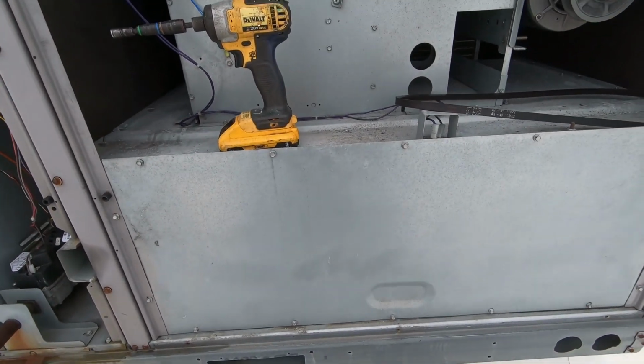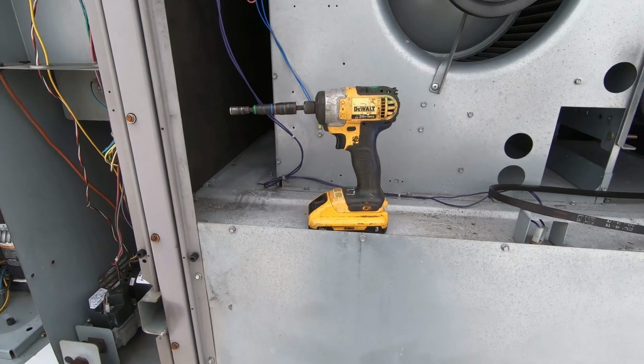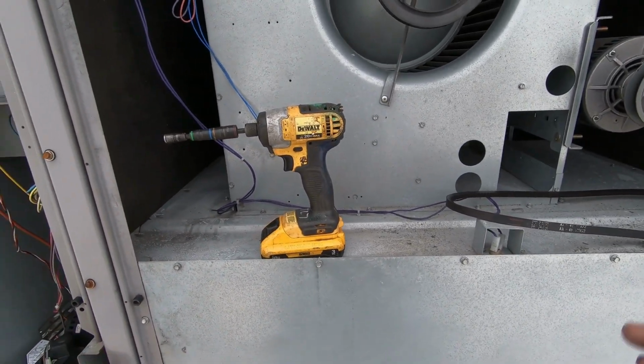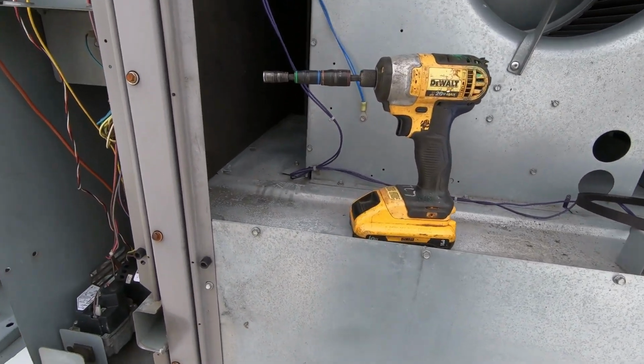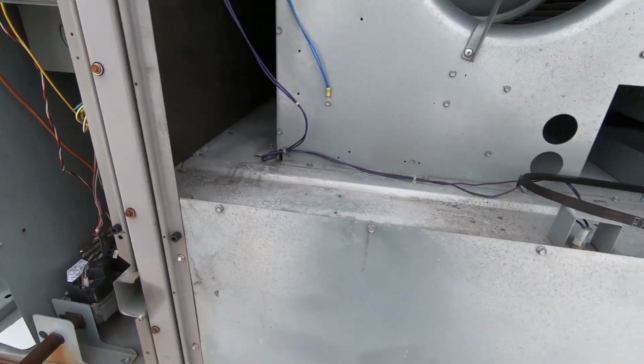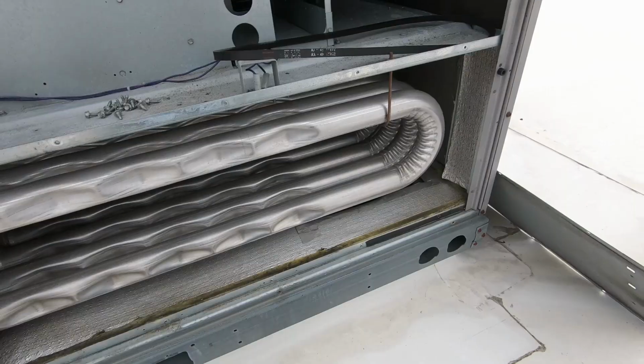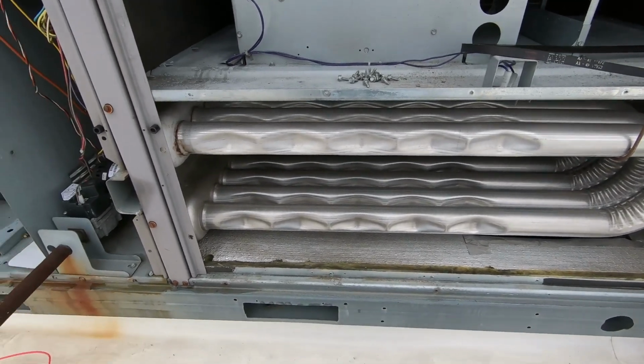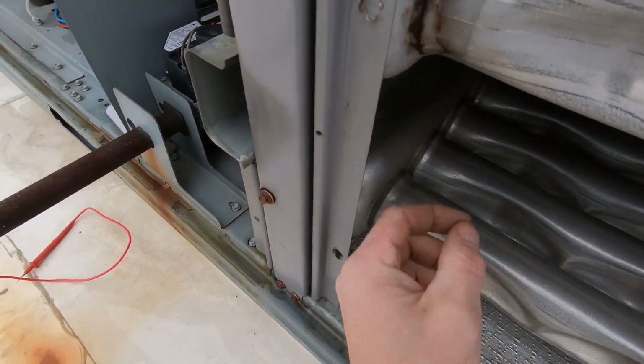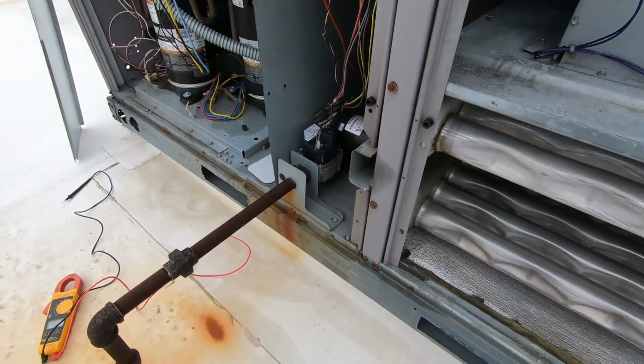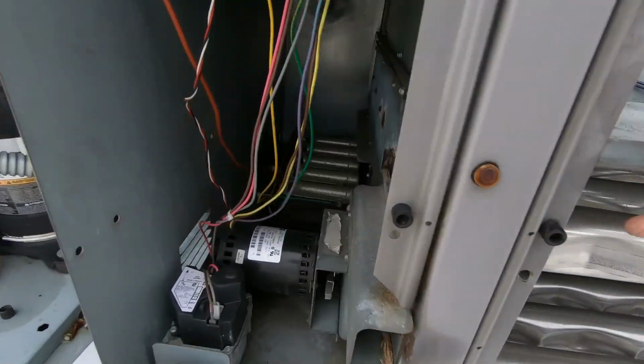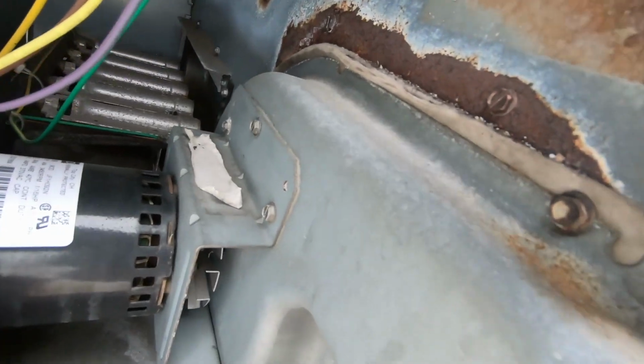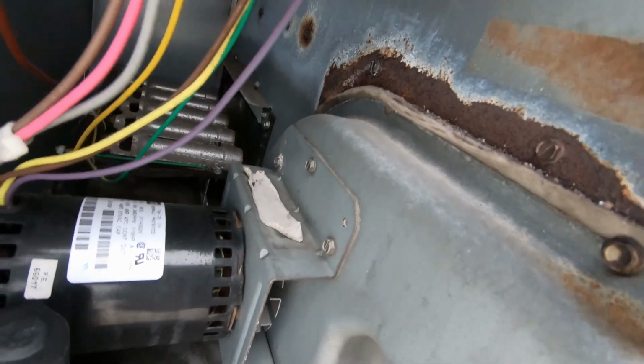I'm gonna check this heat exchanger, because if I said our chances are 50-50, the one that was probably glowing red seems fine. This one's gonna have a crack in it. We'll see. This one is good. I mean, it's got a little bit of rust buildup, but not cracked, not rotted out. The front plate, of course, is starting to rust and rot out.